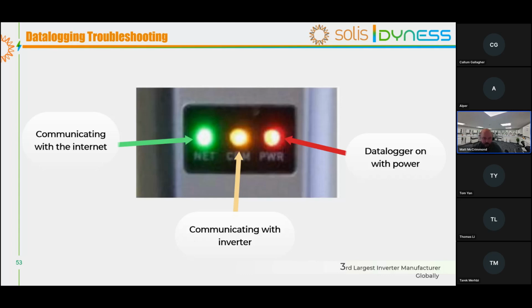If the green light's on and the red light's on, but you don't have the amber light, then that basically means that the data logger stick is not capable of communicating to the inverter. When we discussed earlier about the address of the inverter, one of the things you would see is that you would have no light there if the address was set to 02, because it's trying to search for 01, the first inverter, the master. You then have another couple of things which I'll show you in the next slide on how you can diagnose if it's set to the right address, but you still don't have that light. And then the last one, if there's no red light, then no light will be on. That means that there's no power getting to the actual data logger.